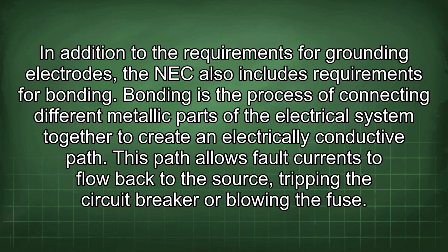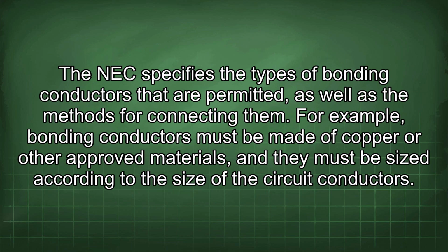In addition to the requirements for grounding electrodes, the NEC also includes requirements for bonding. Bonding is the process of connecting different metallic parts of the electrical system together to create an electrically conductive path. This path allows fault currents to flow back to the source, tripping the circuit breaker or blowing the fuse. The NEC specifies the types of bonding conductors that are permitted, as well as the methods for connecting them. For example, bonding conductors must be made of copper or other approved materials, and they must be sized according to the size of the circuit conductors.